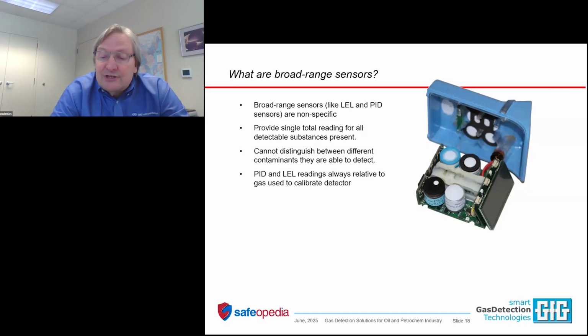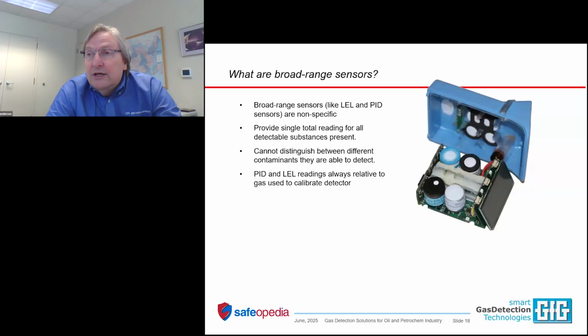LEL and PID sensors are broad range sensors. They are non-specific. The PID, just like the LEL sensor, provides a single reading that comprises the effect on the sensor of all of the detectable gases that are present. So all of the combustible gases, the detectable ones, are going to affect the LEL sensor.